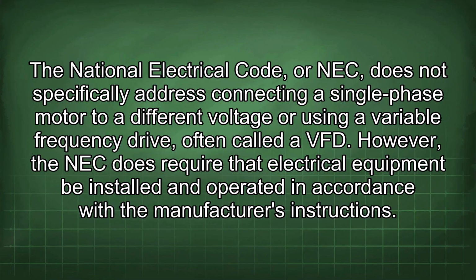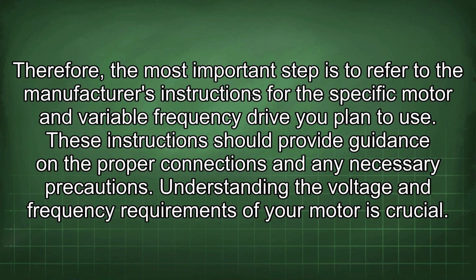The National Electrical Code, or NEC, does not specifically address connecting a single-phase motor to a different voltage or using a variable frequency drive, often called a VFD. However, the NEC does require that electrical equipment be installed and operated in accordance with the manufacturer's instructions. Therefore, the most important step is to refer to the manufacturer's instructions for the specific motor and variable frequency drive you plan to use. These instructions should provide guidance on the proper connections and any necessary precautions.